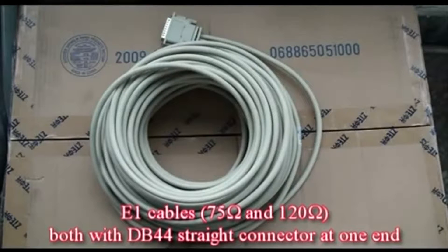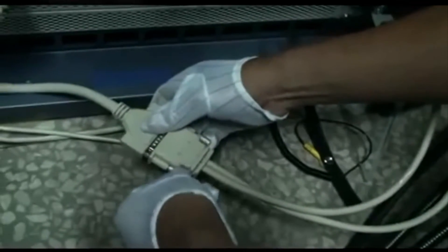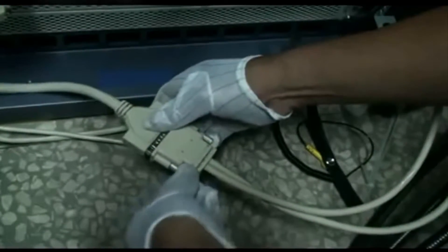Install the E1 cable. There are two types of E1 cables: 75 ohm and 120 ohm, both of which use a DB44 straight connector at one end. Connect the DB44 connector of the E1 cable with the B1 port of the cable on the SA panel.